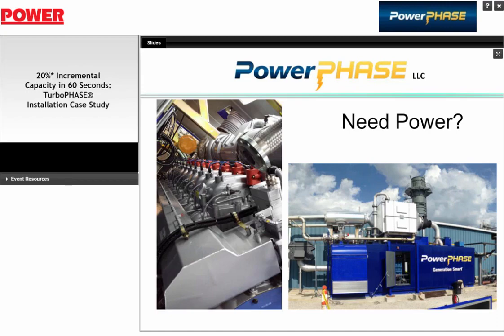Okay. And I think you may have kind of touched on this during your presentation, but a question came in about why and how did the TPM2 air compressor trip? Well, our production module has its own instrument air system, and the Turbophase module itself actually didn't trip. We had rented a small diesel air compressor to feed our instrument air system while we got it hooked up at the plant properly, and it ran out of fuel.